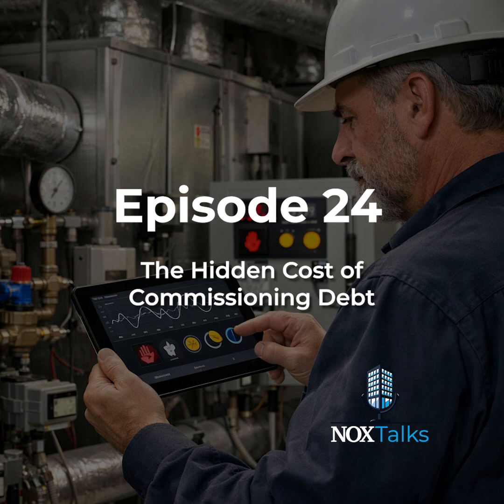Where does commissioning debt usually hide? Start with AHU and VAV reset logic, static pressure reset, supply air temperature reset, minimum airflow settings that never got revisited, then sensor validation, then simultaneous heating and cooling, then schedules that nobody trusts anymore, then point-to-point issues that passed startup but never held up under real operating modes. Most comfort complaints are not mysterious. They're the same few control failures wearing different clothes.